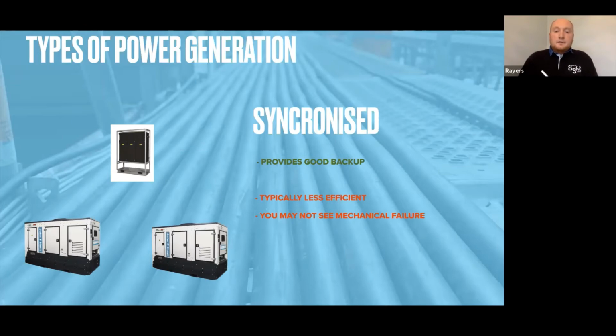The other thing you need to be very careful of is that you don't inadvertently overload the machines. For example, if we were to say that those 2 generators shown there could deliver 100 kVA each, let's say, that's just the term we use. It's a term of measuring the size of the machine. So that means that we can give 100 kVA backed up. So we can only deliver 100 kVA. But between the 2 of them, they will physically deliver 200 kVA because they're both running at the same time.